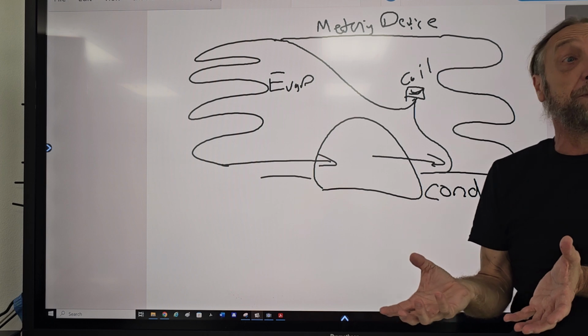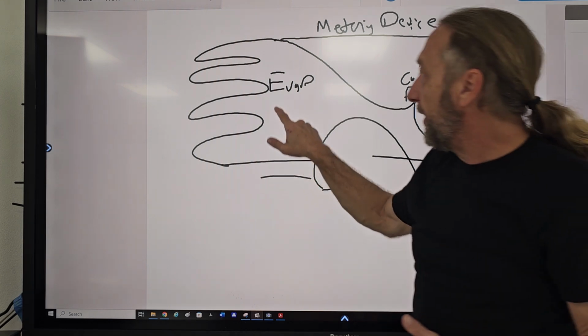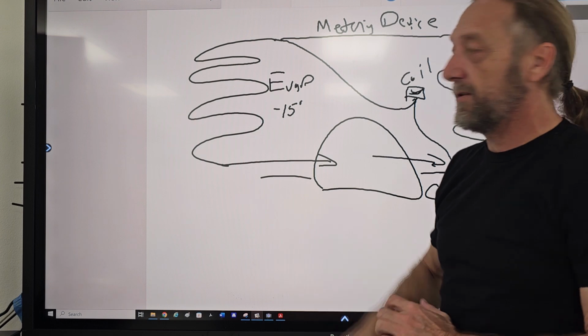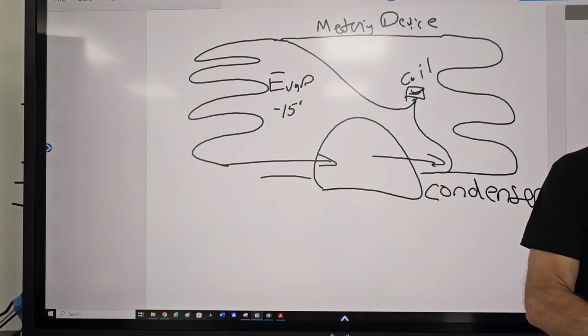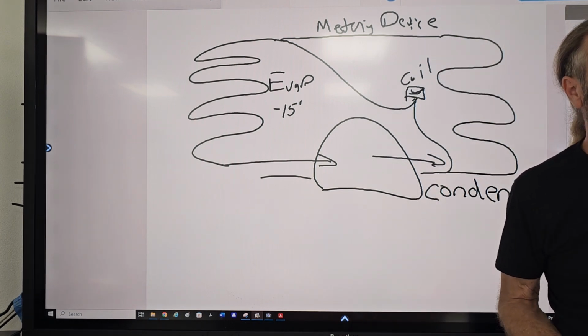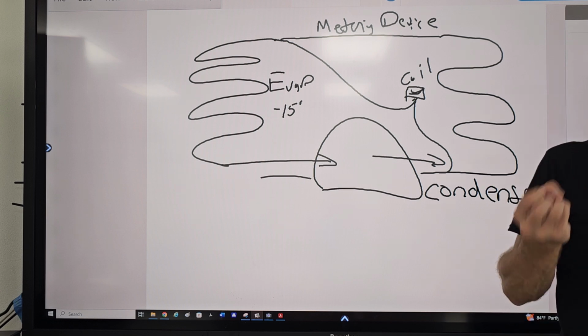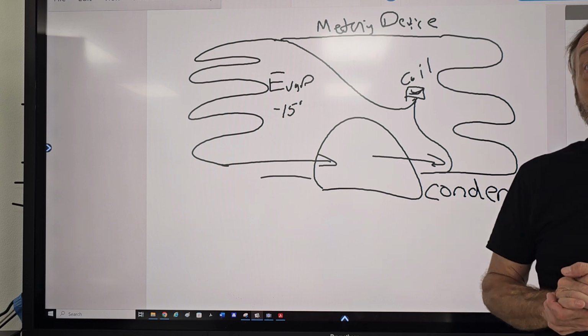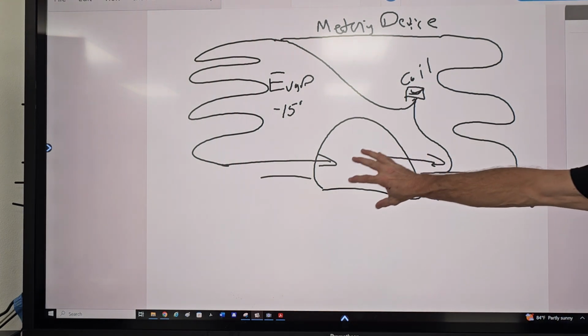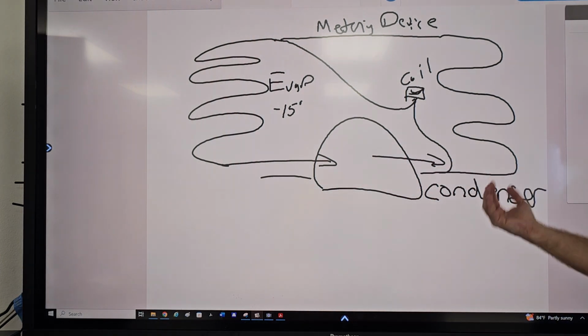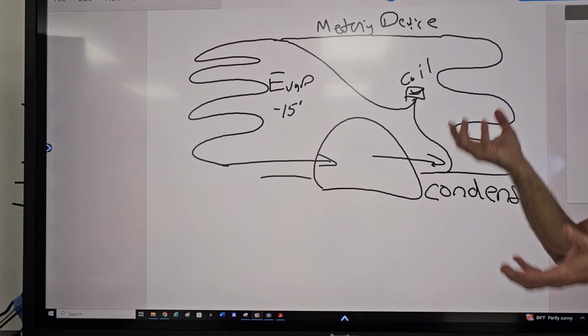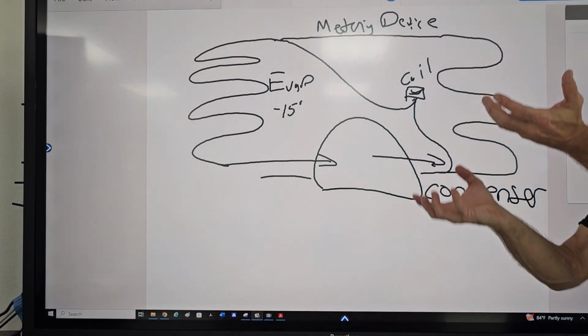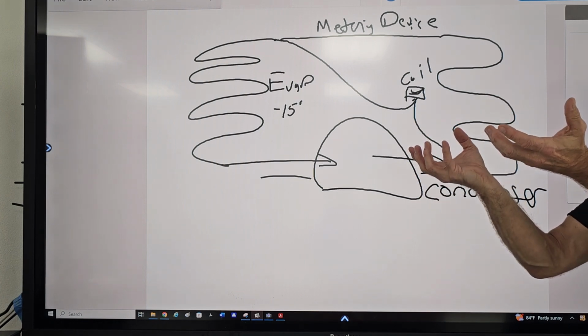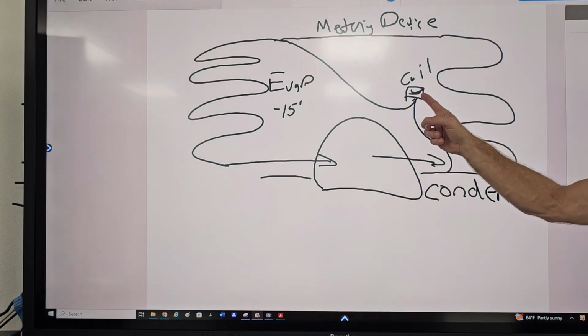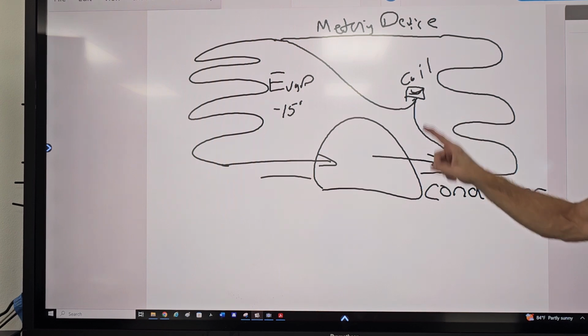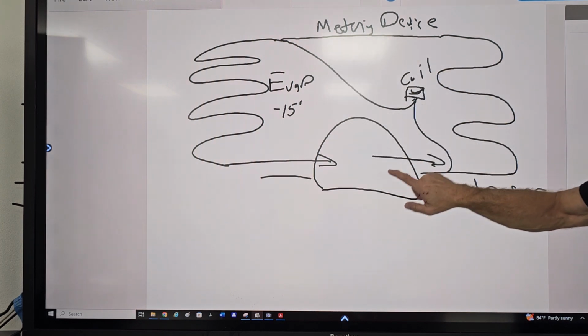But we want to remove the ice. The evaporator, I told you, is negative 15 degrees. Well, if it's that cold, the ice will never fall out. I gotta warm it up. If I use a heating element, it might be too much heat and make it hard to remove. But when a compressor pumps the Freon, it raises the pressure. What did I say at the beginning? When you raise pressure, what are you raising? Temperature. Okay?